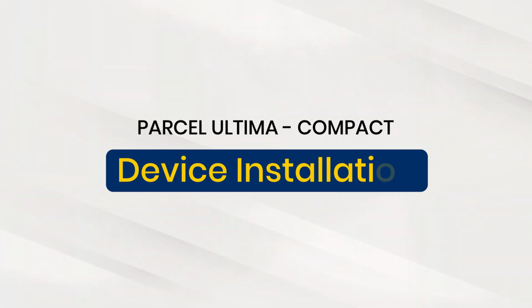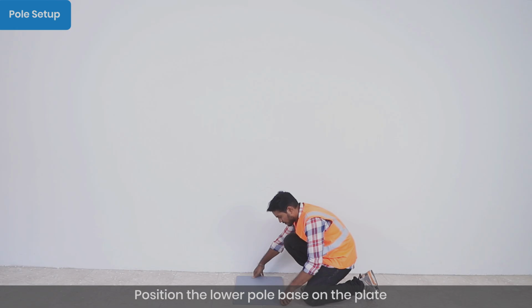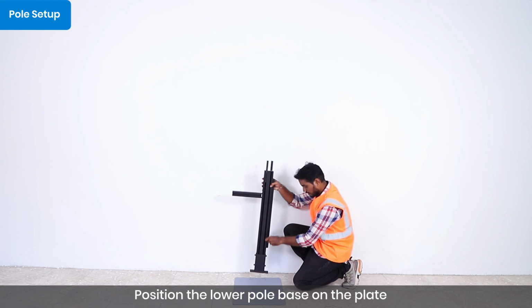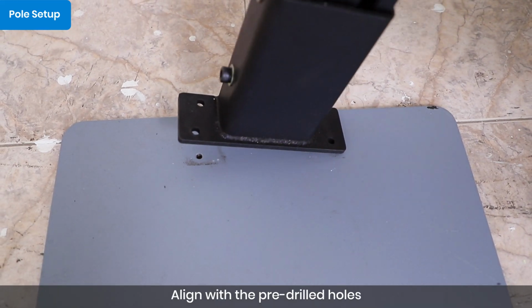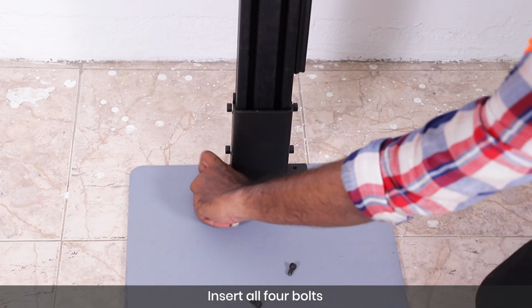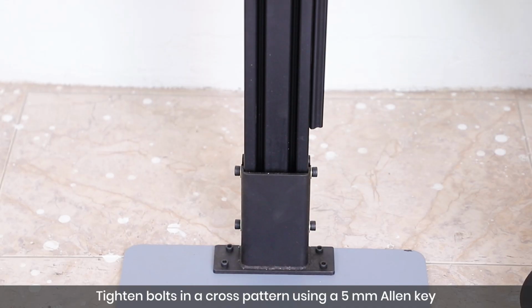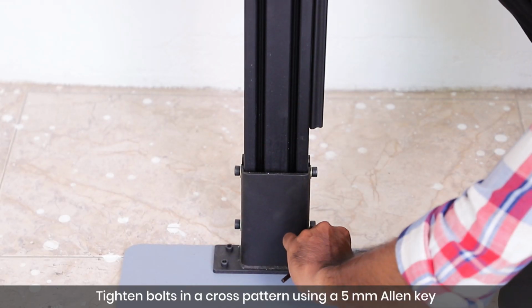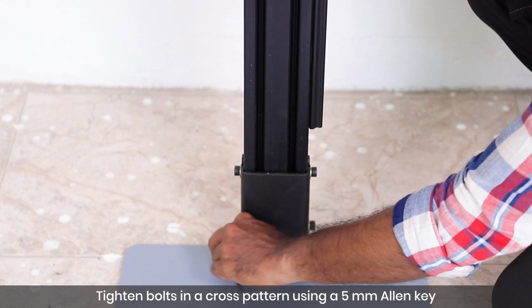Next, begin installing the device. Position the lower pole base on the mounting plate. Align it with the pre-drilled holes. Insert all 4 bolts. Tighten them in a cross pattern using a 5mm Allen key.